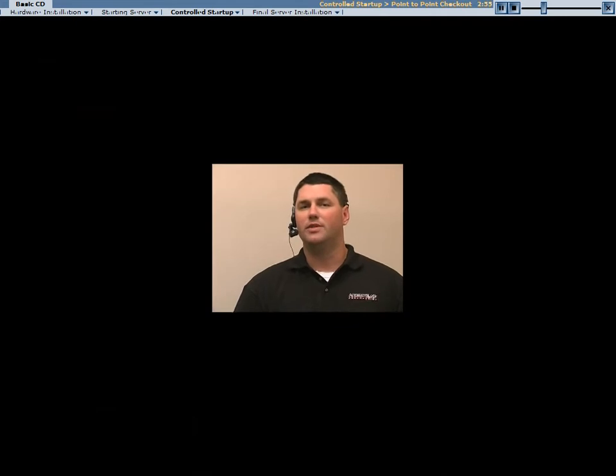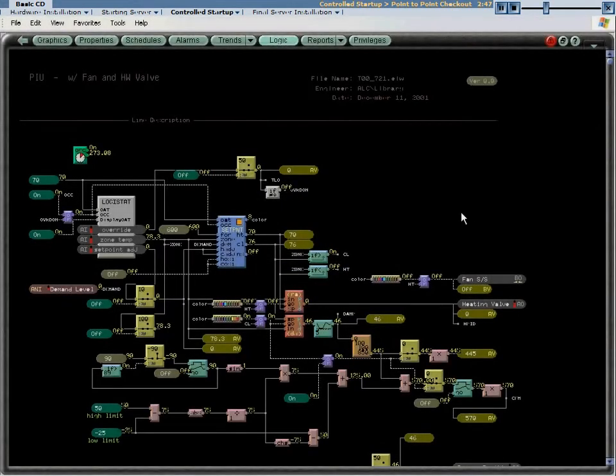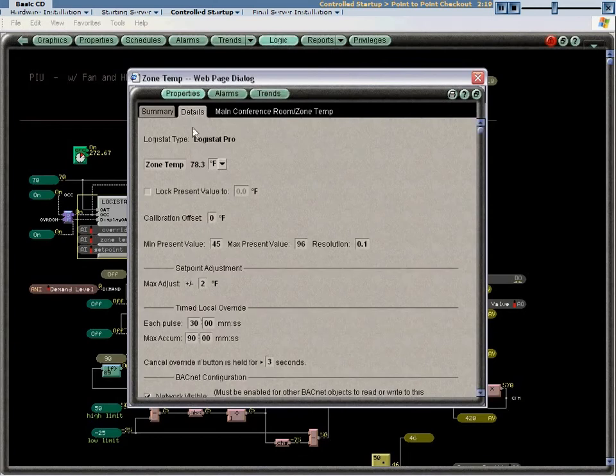For the analog inputs, verify the sensor type and the min-max values are entered correctly on the point details. Read the analog input value on the logic page for that point. For thermistor points only, verify by shorting the two wires together. The sensor should go to full range if shorted. Be aware that you could cause damage to your input or module if you short other signal types. Calibrate the analog input value by adjusting the calibration offset if needed.